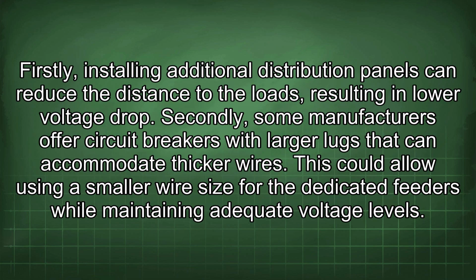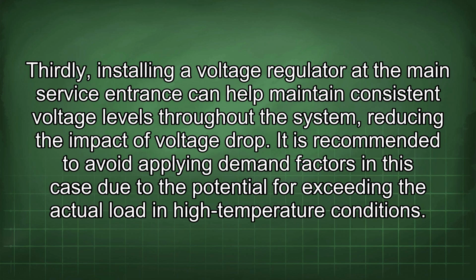Firstly, installing additional distribution panels can reduce the distance to the loads, resulting in lower voltage drop. Secondly, some manufacturers offer circuit breakers with larger lugs that can accommodate thicker wires. This could allow using a smaller wire size for the dedicated feeders while maintaining adequate voltage levels. Thirdly, installing a voltage regulator at the main service entrance can help maintain consistent voltage levels throughout the system, reducing the impact of voltage drop.